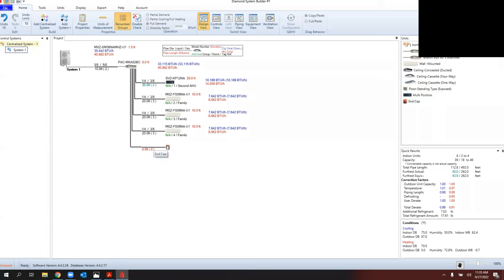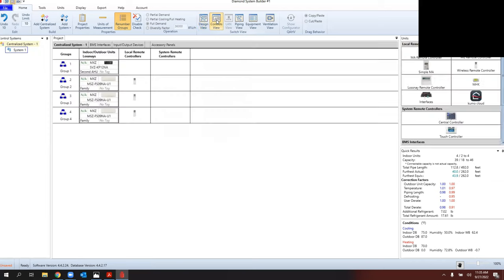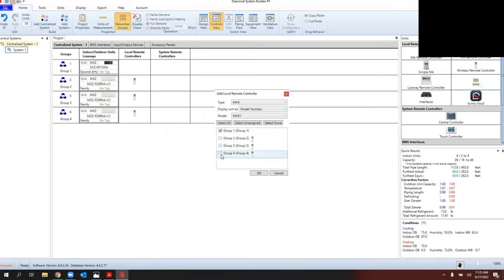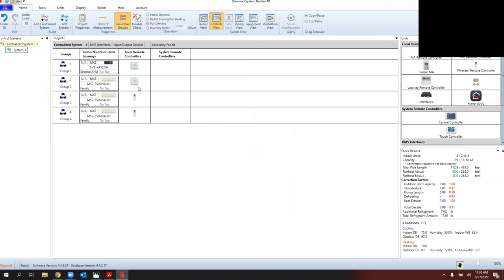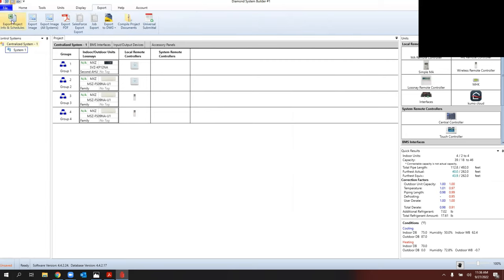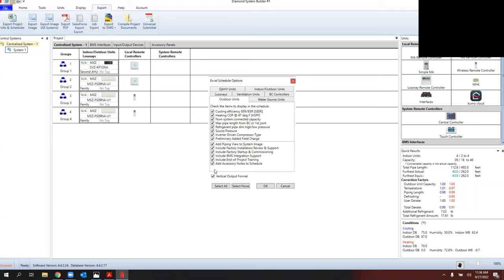If I try to connect another unit, the system throws an error — 'Adding child not allowed' — which is its way of saying you can't add another indoor unit. I'll put an end cap on the remaining port. To export this I need controllers. Going to Controls View, the wall mounts have remotes but the ducted system has nothing listed. I'll click MHK2 — it asks if I want to replace the other remotes with MHK2s as well. There seems to be a glitch where selecting all at once doesn't work; you have to go to each one individually.